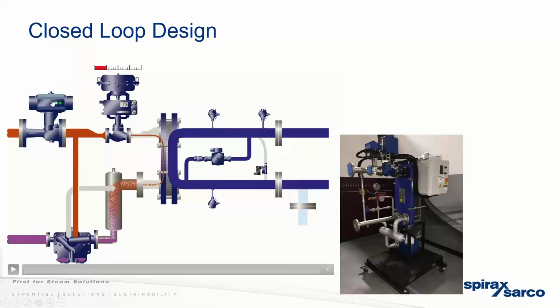On the steam side, there is a high temperature ball valve. And the purpose of this is to ensure a tight shutoff. So should the control valve not have a tight shutoff on the steam, a ball valve will have a tighter seal and make sure that no steam will pass through. This will have a class 6 shutoff, so bubble tight shutoff. Typical steam valves will have a class 4 shutoff, so some slight bubbles can get through. So there's a couple levels of safety on here, as well as continuously monitoring the temperature of the water.